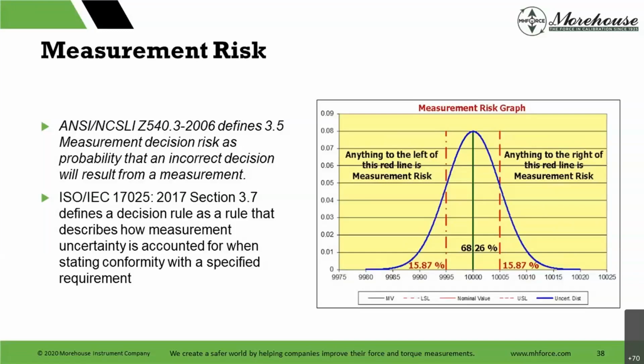The importance of this picture is to bring it all together. When we were talking about repeatability, that gave us the width of this graph. When you plot that graph and put the tolerance lines on it, you can see how much of the graph hangs over, and that is really your measurement risk. Any part of this graph that hangs over is risk, right? So this picture says 68.26% is in, 15.87% is out on the left, and 15.87% is out on the right. Sometimes you'll have some skewness where it goes one way or the other.